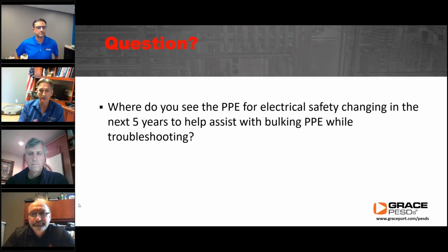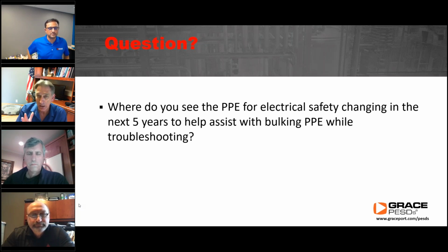It's also a mindset - knowing you have to wear arc rated clothing, shock and arc rated equipment, in an energized or potentially energized condition. If you're testing for absence of voltage and don't have a safe test point, and you have to open the equipment, you must be suited up for shock and arc flash to test for absence of voltage.